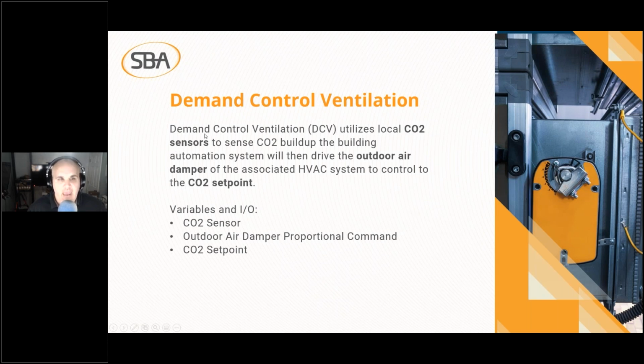Demand control ventilation utilizes local CO2 sensors, typically in the return duct or on a space wall. The problem with having them in the return duct is if that unit turns off, you have no air drawing through them, so you've got a less reliable value in unoccupied scenarios. That's why I usually like to have them in the space on a wall, if possible, but not every space can accommodate that.